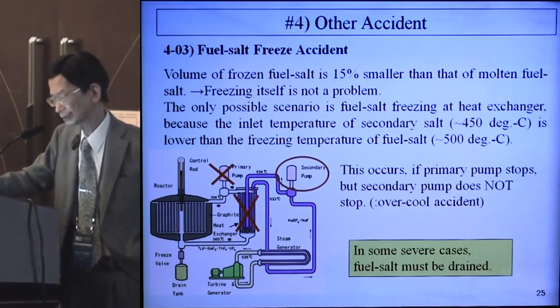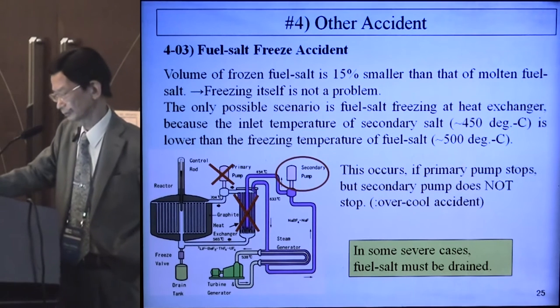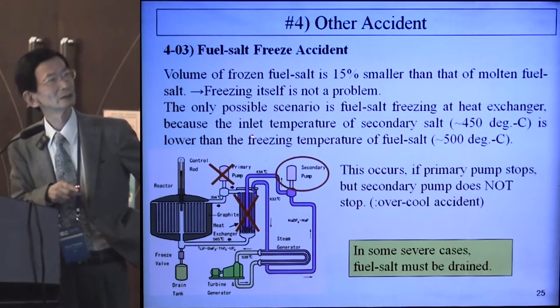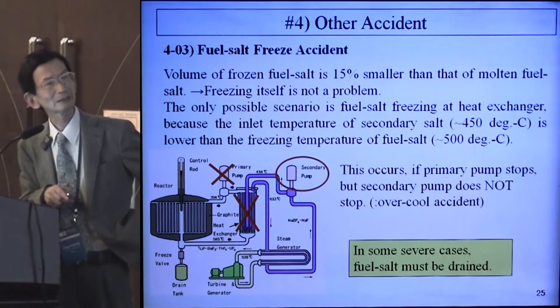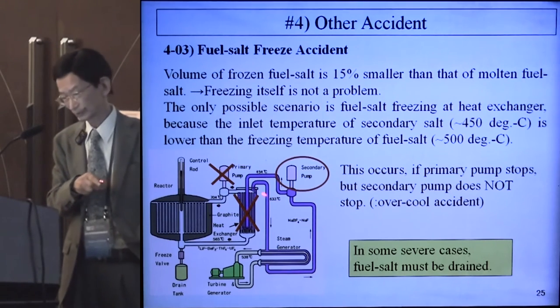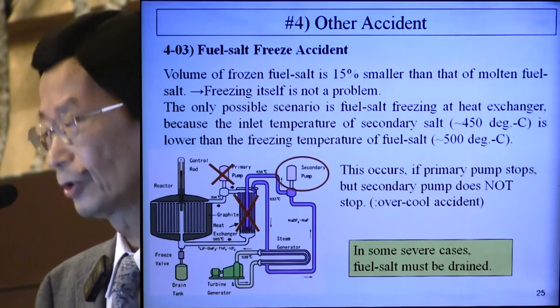4.03 is the fuel salt freeze accident. The volume of frozen fuel salt is about 15% smaller than molten fuel salt, so freezing itself is not a problem. The only accident scenario is fuel salt freezing at heat exchangers, because the inlet temperature of secondary salt is lower than the freezing temperature of fuel salt. This occurs if the primary loop stops but the secondary pump does not stop, overcooling the fuel salt. In severe cases, fuel salt must be drained.